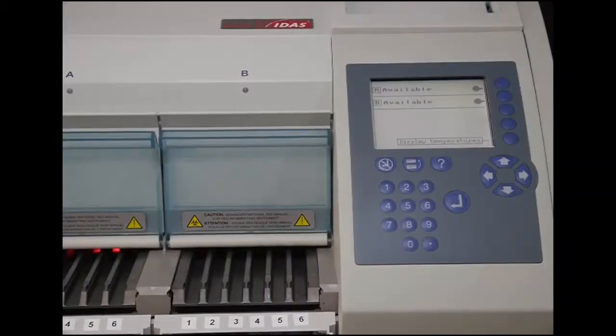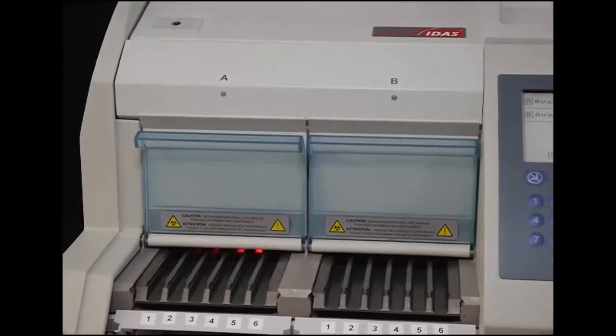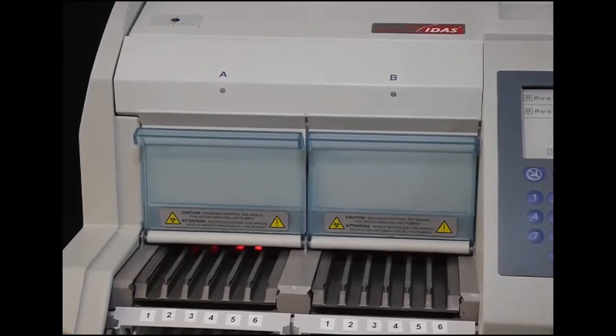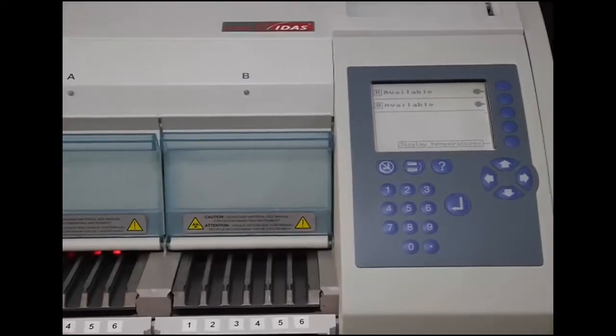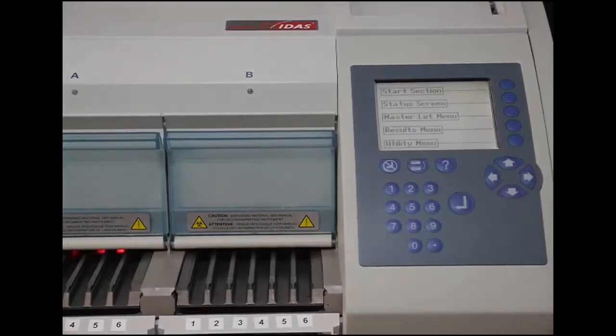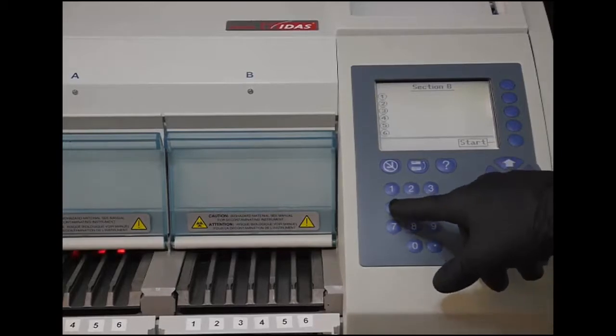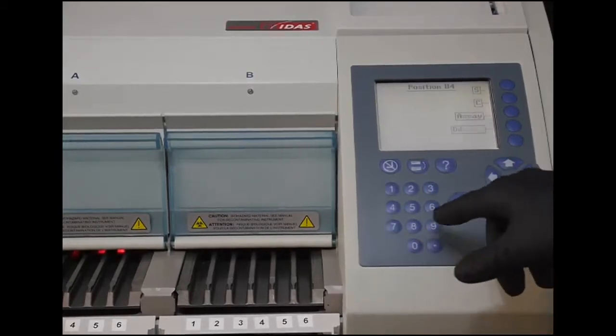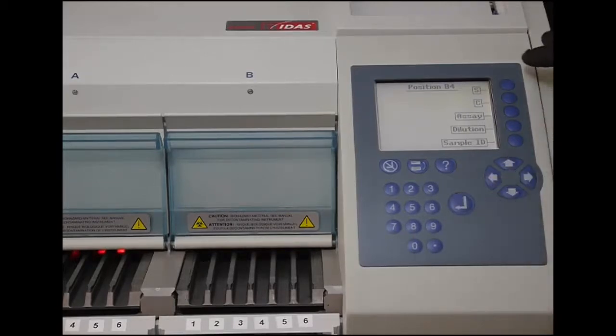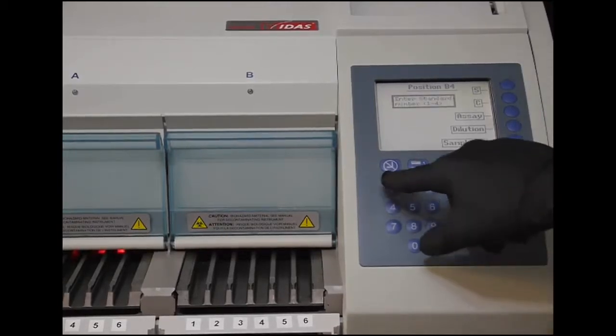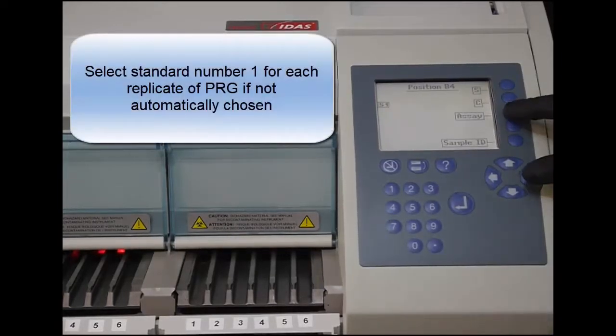Now to order the test, I'll select which bay or section that I will use. There's section A with positions 1 through 6 and section B positions 1 through 6. To order the test, I'll return to the main menu, go to status screen, select the bay I wish to use, select the positions I wish to place my test strips in. For this purpose, I'll be in B4, 5, and 6. Now in position B4, we have the option of selecting a standard, control, or simply a sample.